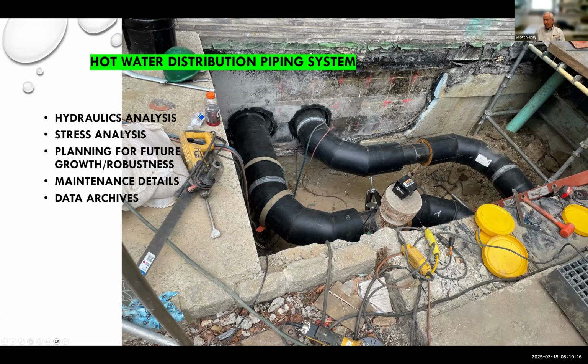The piping is direct buried rather than building expensive steam tunnels, and the thermal expansion can be taken up by foam pads at strategic locations. We loop the system for redundancy of service, where you can have a branch out of service but still feed buildings from another direction. We've added valves at strategic locations and added tees for system extensions of service. We've been careful about adding vents and drains at strategic locations. We inspect every weld and pressure test every pipe section.